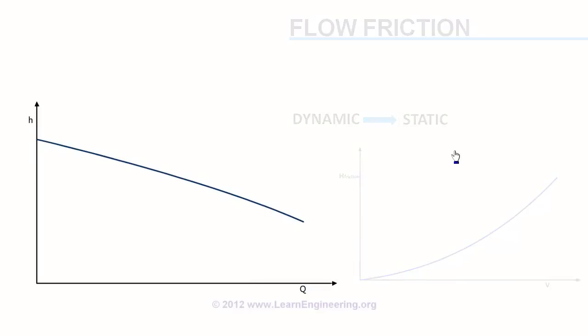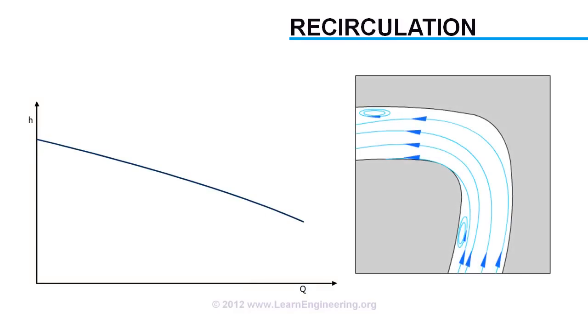Next is due to recirculation effect in the flow. When flow is below the design flow rate, recirculation losses become predominant as shown in the figure. When the pump operates at its design flow rate, recirculation loss is almost zero.